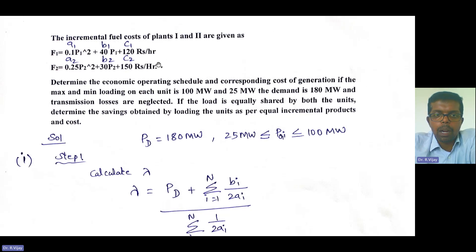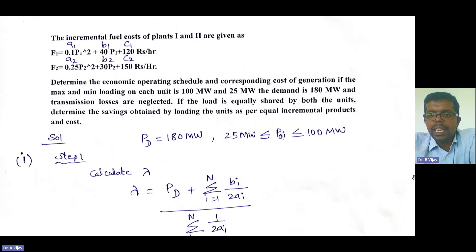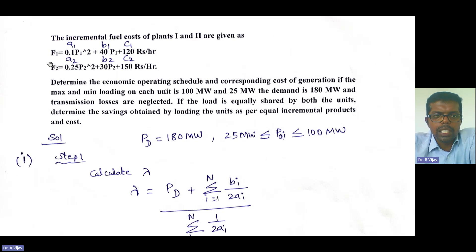This is the data given in the problem. The demand is clearly given as 180 megawatt. Minimum and maximum operating limits are also given: 25 megawatt ≤ PGi ≤ 100 megawatt. To solve using the lambda iteration method, you need to mark A1, B1, C1, A2, B2, and C2 from the incremental fuel cost functions F1 and F2 given in the problem.